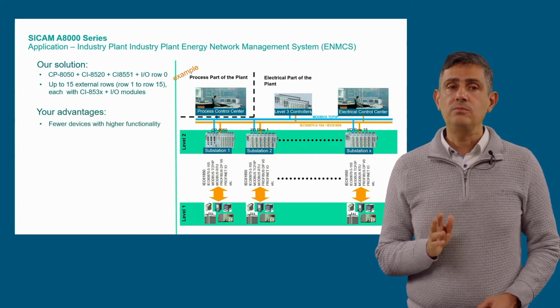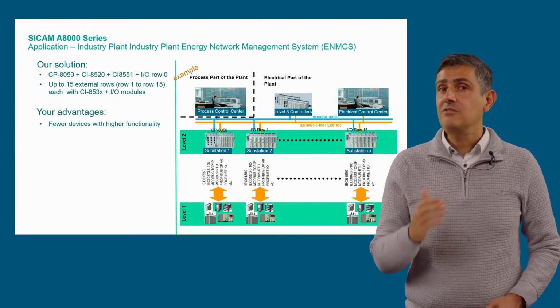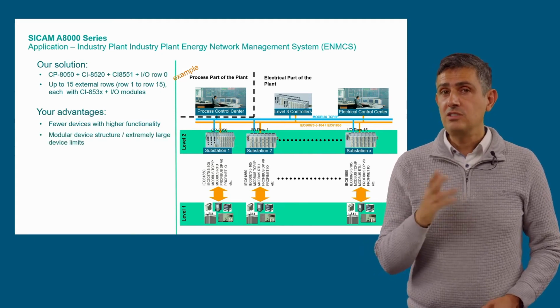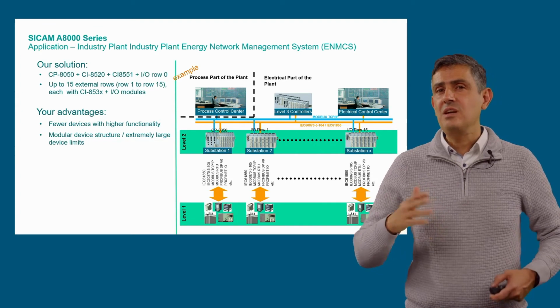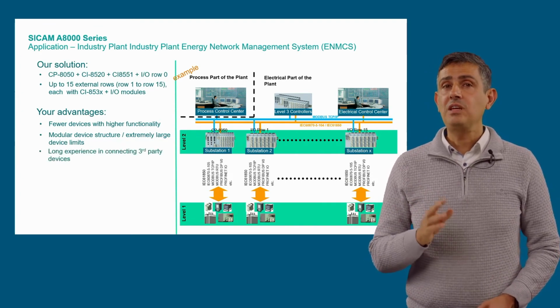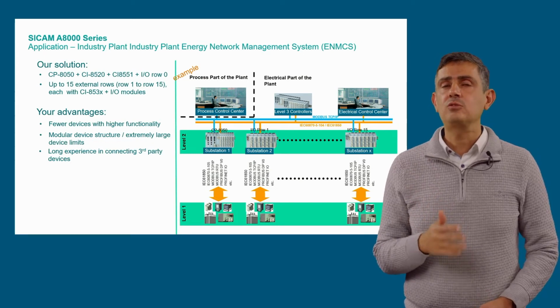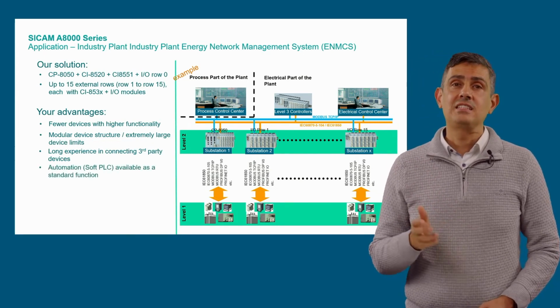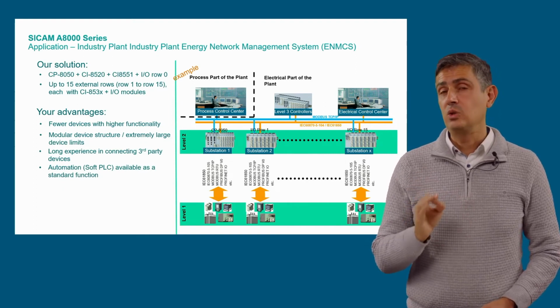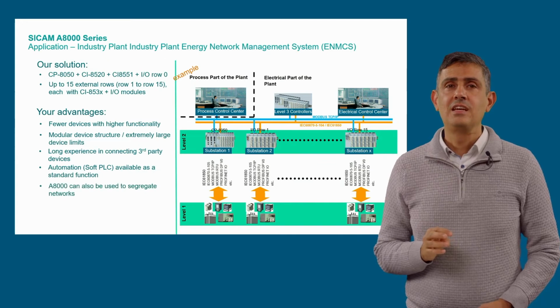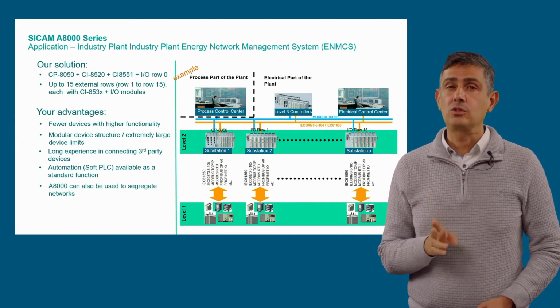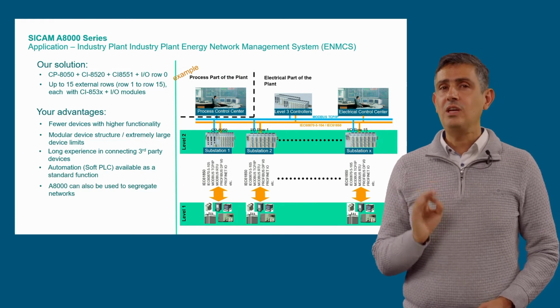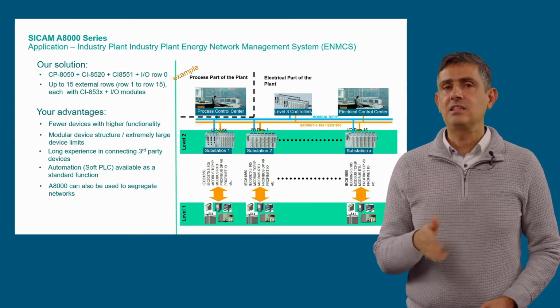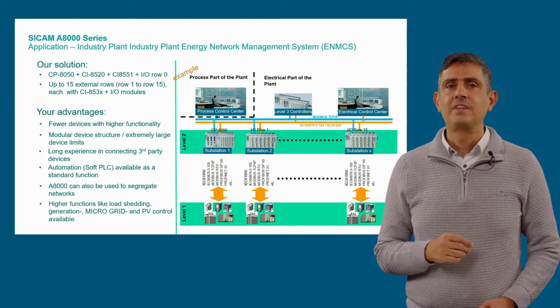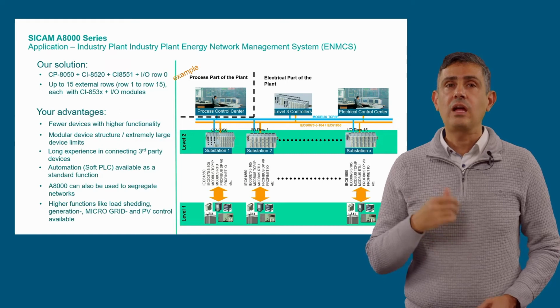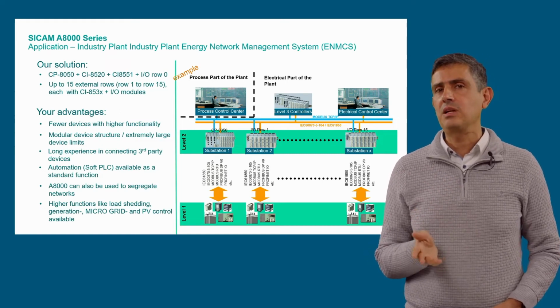Your advantages with this solution: for such a large system, you need fewer devices with higher functionality. The modular structure allows for the easy expansion of the system with extremely large device limits. You can make use of our large experience connecting third-party devices to our SICAM A8000 systems. The soft PLC features available are state-of-the-art, so you can expand your automation to new limits. You can also use the SICAM A8000 to segregate networks, so you could have maximum cybersecurity while also keeping the communication flow between the different system elements. In addition, higher functions such as load shedding, generation control, microgrid, and photovoltaic plant control are available.